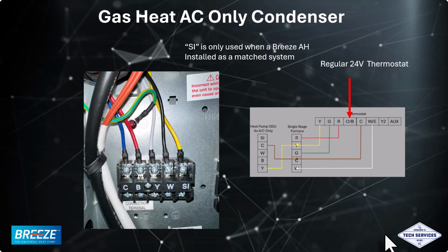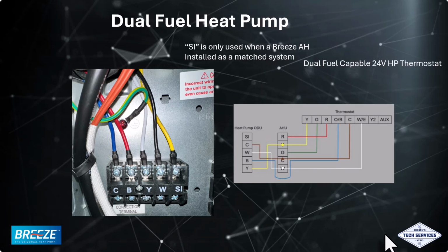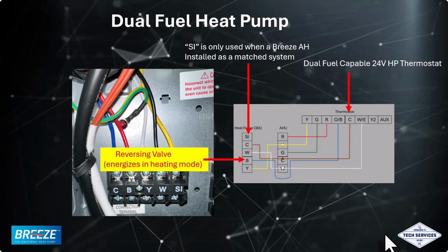Typical regular gas thermostat. You'll wire your Y terminal to the outdoor unit and your common terminal to the outdoor unit. Dual fuel heat pump. You'll need a dual fuel capable 24 volt heat pump thermostat. The reversing valve energizes in the heating mode, which is going to be the B terminal. You'll wire common and Y to the outdoor unit.